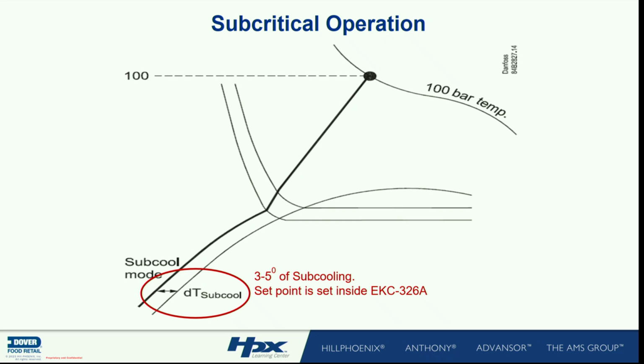What if when he's regulating you to 44%, what he's really doing, and I can look in the controller and see a reference pressure and an actual pressure, what if I raise the saturation point to 75 and I don't touch the drop plate temperature? Would that be 5 degrees of subcooling? Yeah. If I walked in and I took the pressure and I read 894 and then I put a thermocouple on the drop plate and it was 70, how many degrees of subcooling? 5 degrees.